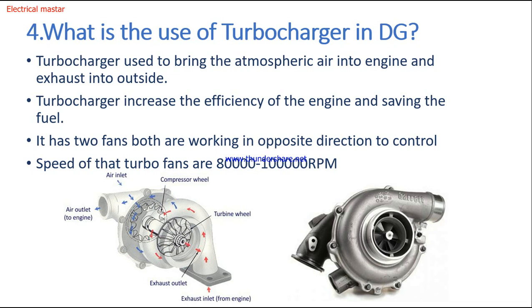Fourth question: what is the use of a turbocharger in a diesel generator? The turbocharger brings atmospheric air into the diesel engine and exhausts gases outside. It also increases the efficiency of the engine and saves fuel. The turbocharger normally has two fans — you can see this picture — coupled to each other, rotating in opposite directions. One fan inlets air into the engine and the other exhausts gases outside. The speed of these fans is very high, around 80,000 to 1,00,000 RPM.